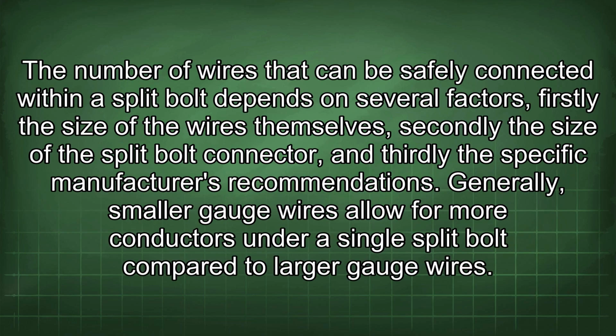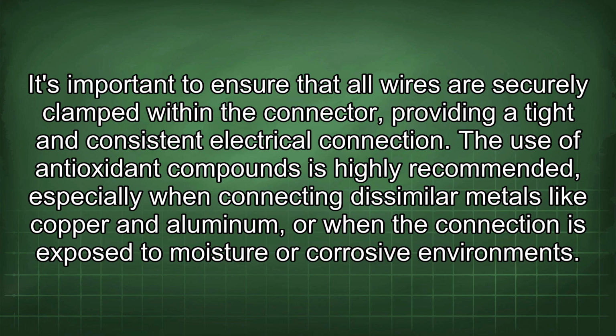The number of wires that can be safely connected within a split bolt depends on several factors. Firstly, the size of the wires themselves. Secondly, the size of the split bolt connector. And thirdly, the specific manufacturer's recommendations. Generally, smaller gauge wires allow for more conductors under a single split bolt compared to larger gauge wires. It's important to ensure that all wires are securely clamped within the connector, providing a tight and consistent electrical connection.